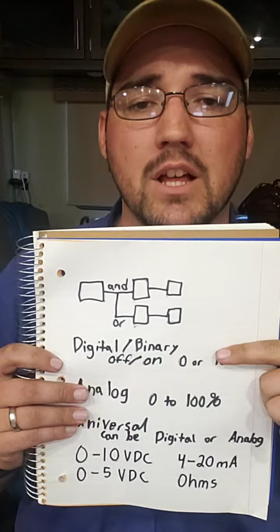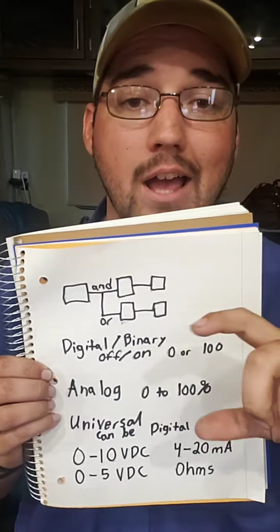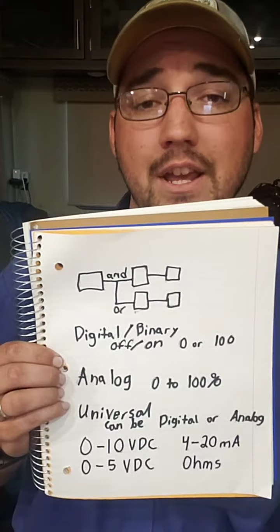What trips a lot of guys up is when you look at a DDC controller, you'll see AIs, AOs, DI, DO, or it may be a BI, a BO, or even a UI and UO. All of those are a description of the type of input or output that it is. So the I and the O at the end just tells you is it an input, meaning it's giving a signal into that controller, or if it's an O, then it's an output leaving the controller.